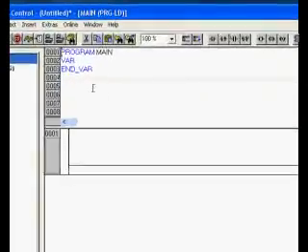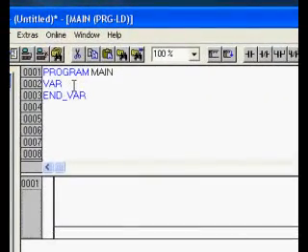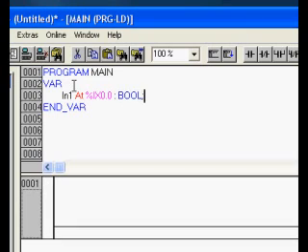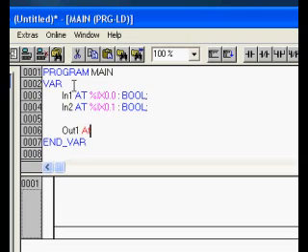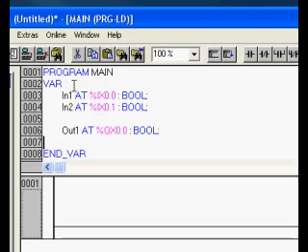Okay, so now the very first step, I'm going to create some variables. TwinCAT is tag-based, so I'm doing this manually, you can do a table if you want. So what I'm typing, I'm creating variables and declaring an address. Now these addresses are just addresses I've made up to use, and you need to do that whenever you're going to link physical I/O. And in order to run TwinCAT, you have to have what's considered a sync master, which is at least one physical I/O. So that's why I'm just going to declare two inputs and two outputs.